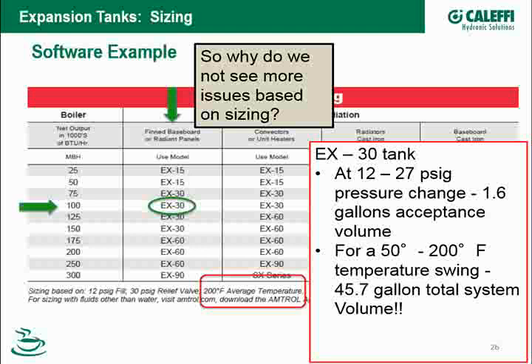I've actually sat down and worked the numbers back. If I'm going from 12 to 27 psi, and I am running between 50 to 200 degrees Fahrenheit as my average system temperatures, low and high, a Model 30 Extrol is good up to around 45 gallons of system volume. So you look at that, and that gives you a lot of leeway in system design and not having to worry about pushing up to the maximum limit of that tank.